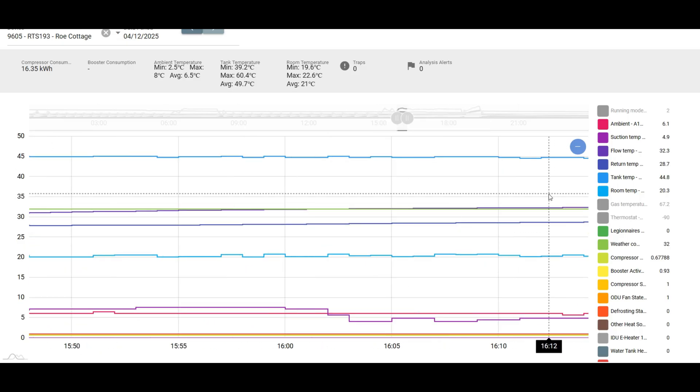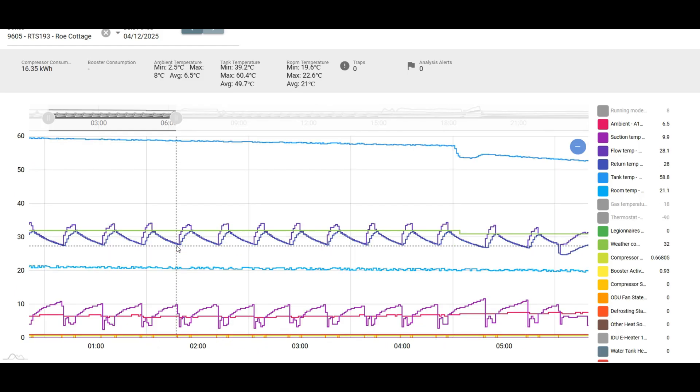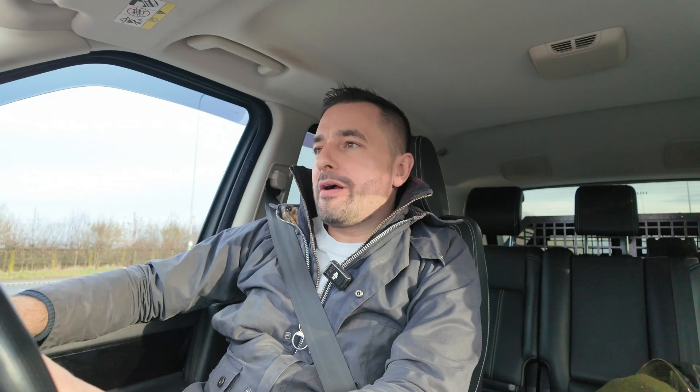We can choose what we monitor and adjust every parameter — anything adjustable on the main controller within the heat pump, we can adjust remotely. On my phone right now I can access any site I've installed over the years and pull data back from any point, from when the unit was in the climate room at base, through delivery on site, and its entire run life — because we store data on a central server, not on the unit itself. Some systems only let you view data live without recording it; that's remote access. Remote monitoring records data — some units store 30 days, 7 days, a year — but I record everything throughout the life of the unit. As geeky as it is, I love it. I can go back over 18 years and look at weather data and everything.